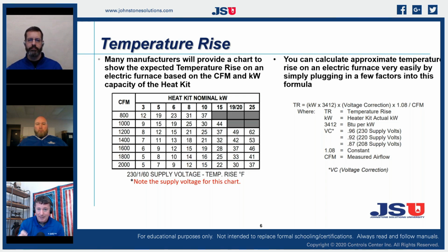Some of our equipment limits what we can even set that temperature rise to. If I look at like the Daikin 1+ thermostat on an inverter system, it will not allow me to decrease my airflow for the electric heaters. It says, hey, I want around a 30 to 35 degree temperature rise, and I'll do the adjustments to make sure that happens. And so it's preset. So we can increase the airflow a little bit, which is going to run down our temperature rise, but we cannot raise the temperature on that electric furnace because it's trying to maintain the integrity of the heating elements. It wants those heating elements to run a long time, hopefully a lifetime.